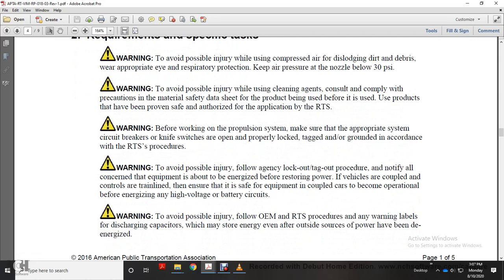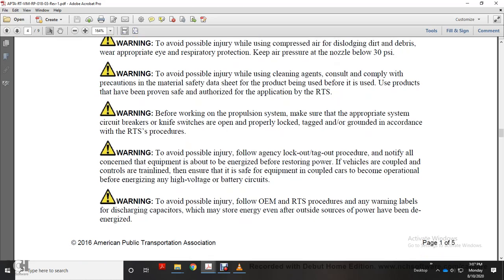Warning: before working on the propulsion system, make sure that the appropriate system circuit breakers and switches are open, properly locked, tagged, and grounded in accordance with the railway transit system procedures. Warning: to avoid possible injury, follow the agency lockout tagout procedure. Notify personnel that the concerned equipment is about to be energized before restoring power. If vehicles are coupled with the controls or train line, ensure the safety of the coupled cars before energizing high voltage battery circuits.